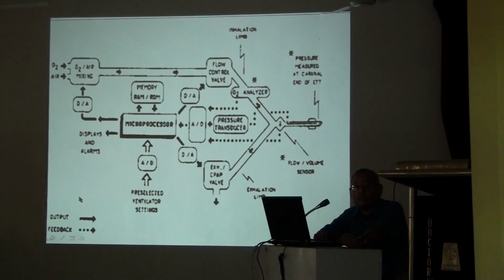Before going to the sophistication, I'll tell you about the essential components of a ventilator. What are the essential components of the ventilator? This is an air mixer I have made through this mixing device. Just like in our anesthesia, those who are anesthetists may know, we give nitrous oxide and oxygen, 4 liters, 2 liters like that. So we mix the gases according to our wishes. Here also it is the same thing. It may be a flow meter, it may be a proportional controller valve, anything. Whatever the technology, ultimately it is basically a mix of gas, and it goes out from this bonnet to the outside patient circuit.